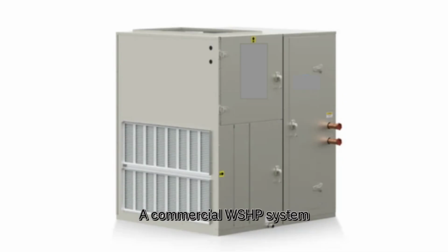A commercial WSHP system connects multiple individual heat pumps to a common hydronic loop. Each WSHP serves its own zone, for example, an office, classroom, or apartment, extracting or rejecting heat to the loop as needed. The loop itself is kept within a broad temperature range, typically between 60 to 90 degrees Fahrenheit.